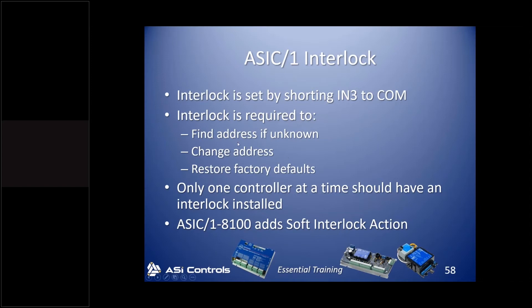The interlock is used for a few different functions: to find the address of a controller when you don't know it, to change the address, and — less commonly now — to restore the controller to factory settings with one click. More commonly, people just load a configuration with the desired settings. It's important that only one controller at a time has the interlock installed, because when changing an address, you're essentially saying 'change the address of the controller with the interlock.' If multiple controllers have the interlock installed, they'll all change addresses, which is usually not what you want.